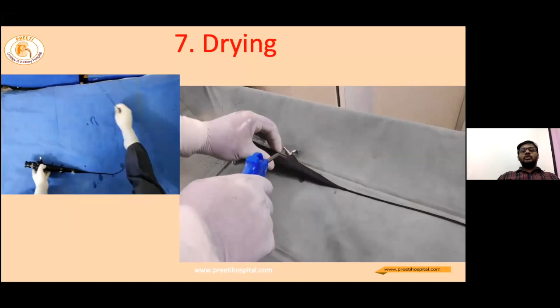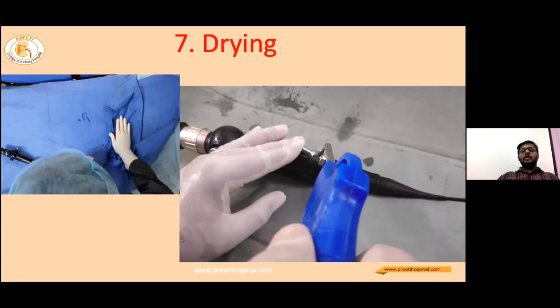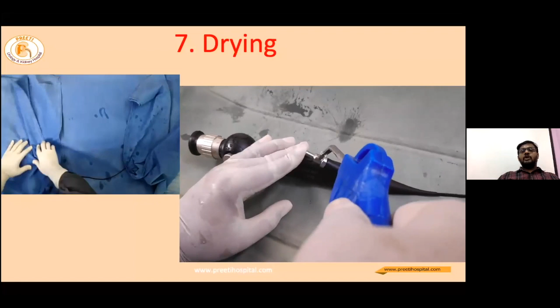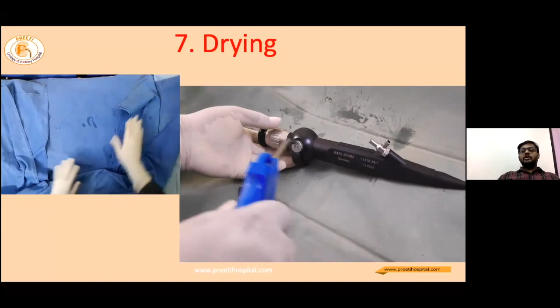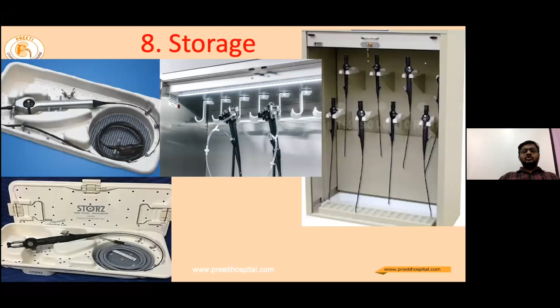Then comes the drying of the scope. The main aim of drying is to make sure that all the water or chemicals inside the channels are dried. This can be helped by using special air guns, and also by pushing 5 to 10 ml of 70% isopropyl alcohol into the channels so that the drying process is improved. After drying, the scopes should be placed in the manufacturer-provided packages, or hung safely in containers so that drying is improved.